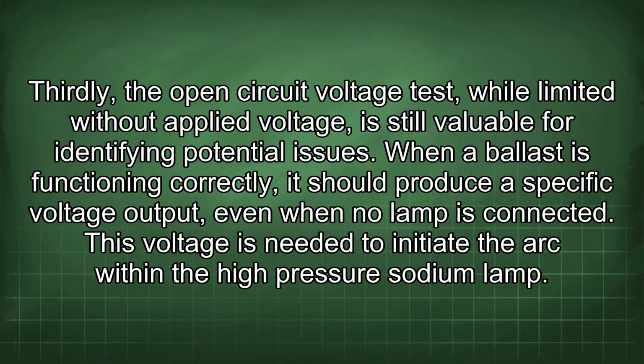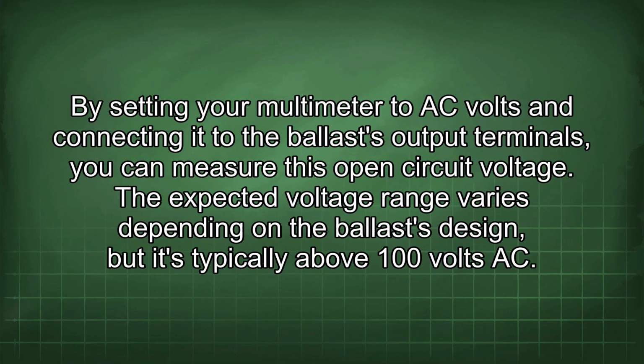Thirdly, the open circuit voltage test, while limited without applied voltage, is still valuable for identifying potential issues. When a ballast is functioning correctly, it should produce a specific voltage output even when no lamp is connected. This voltage is needed to initiate the arc within the high-pressure sodium lamp. By setting your multimeter to AC volts and connecting it to the ballast output terminals, you can measure this open circuit voltage. The expected voltage range varies depending on the ballast design, but it's typically above 100 volts AC.